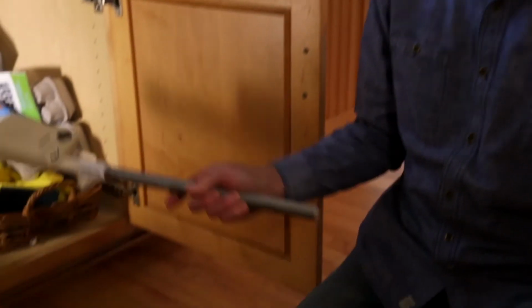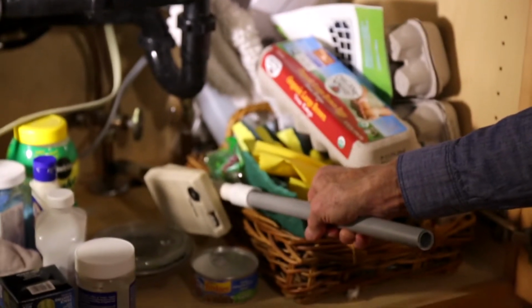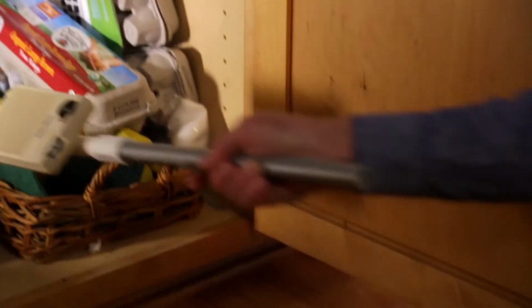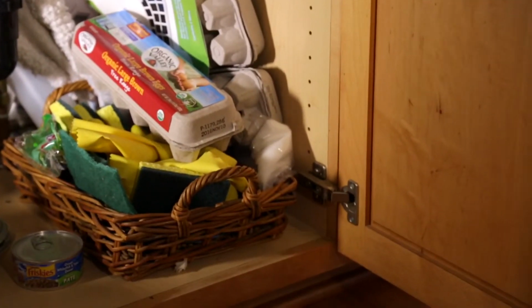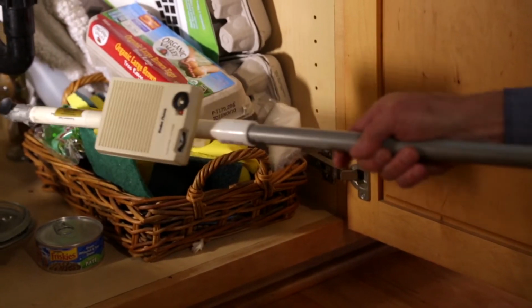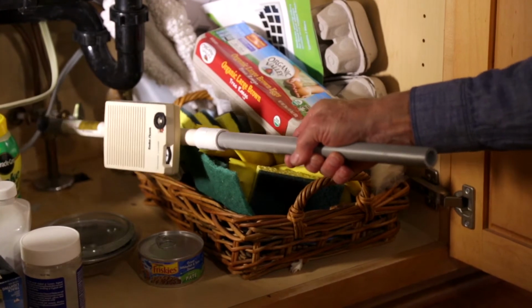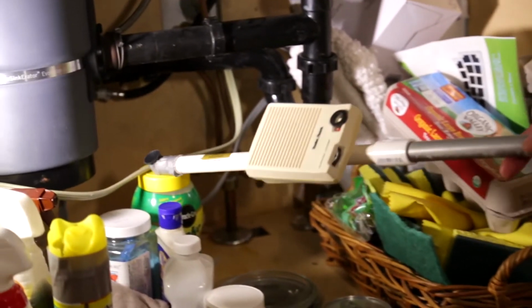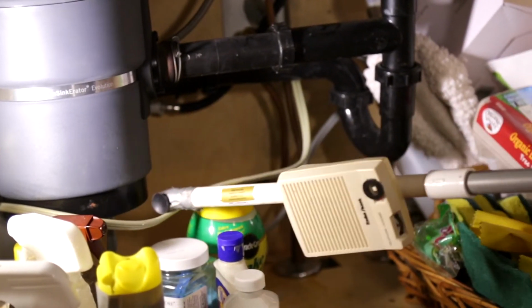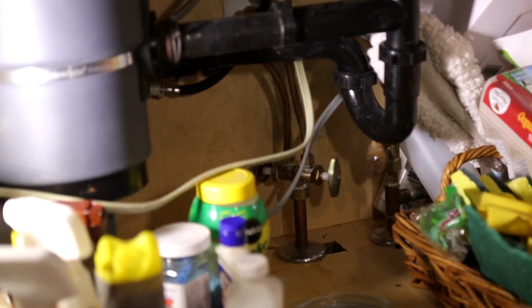And we discovered that with the use of our trusty buzz stick in the kitchen cabinet. We found current flow coming up the water pipe into the kitchen cabinet, and then we noted that it is not going to the garbage disposal, and that's what this line is for, but we did find it going to the dishwasher over here.